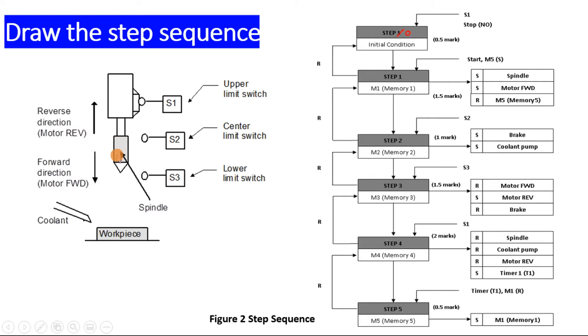When the machine arrives at step 3, which is the lower limit switch S3, it will reset the motor forward, set the motor reverse, and reset the brake — because it is going to move up at high speed. In step 4, when the drill comes back to its initial condition, you reset the spindle, stop the coolant pump, stop the reverse motor, and start timer 1 for the 1-minute delay. After that, you need to come back to step 1, so you add one more memory which will reset the overall step and come back to step 1 again.